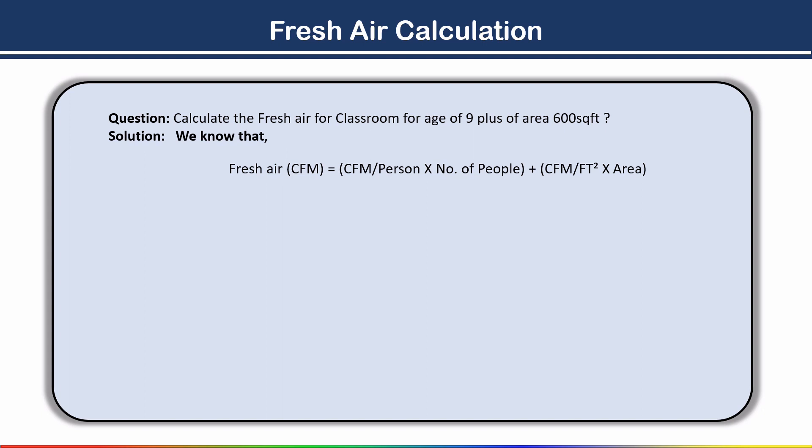CFM is the imperial unit of air flow rate — Cubic Feet Per Minute. The metric unit is cubic meters per second. Here we are working in imperial units, so we use CFM. Fresh air CFM = (CFM per person × number of people) + (CFM per square feet × area).